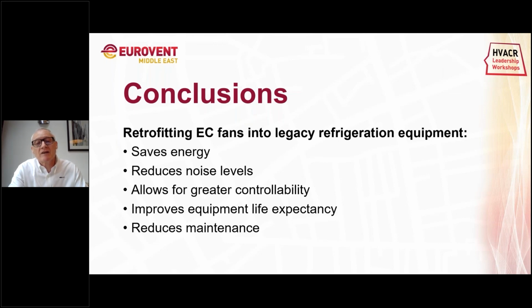The bearings in an EC fan run a lot cooler, and as we all know, bearings are one of the biggest failure points on a fan. So with an EC fan running cooler, the equipment lasts a lot longer. An EC fan's life expectancy is on average about 70,000 hours compared to a standard AC fan motor, which would be about 40,000. Typical applications can increase depending on the environment.